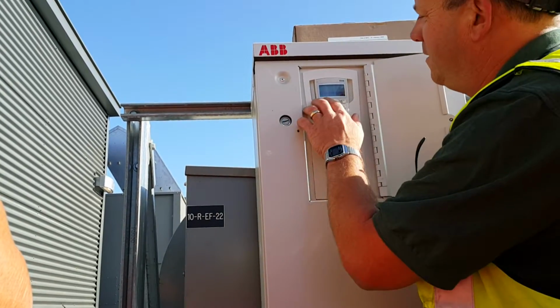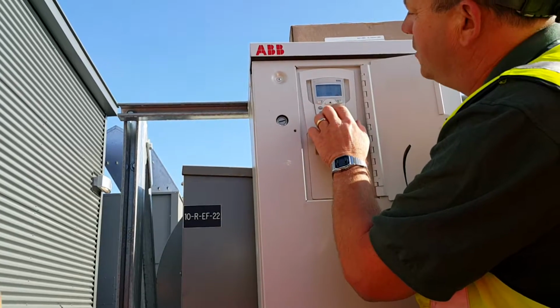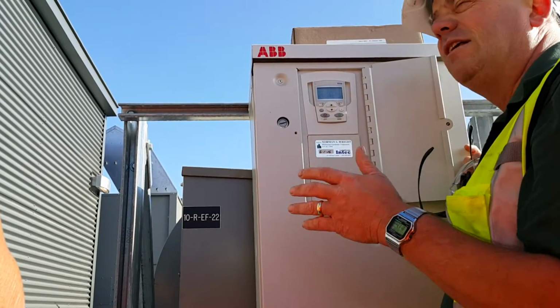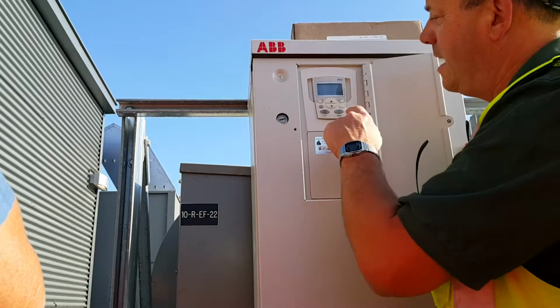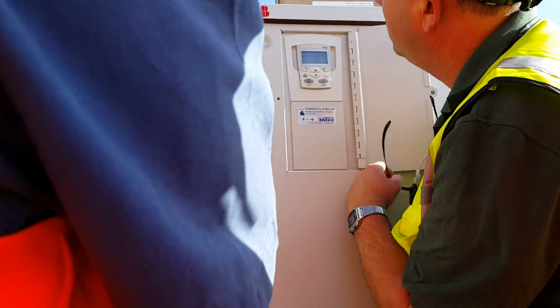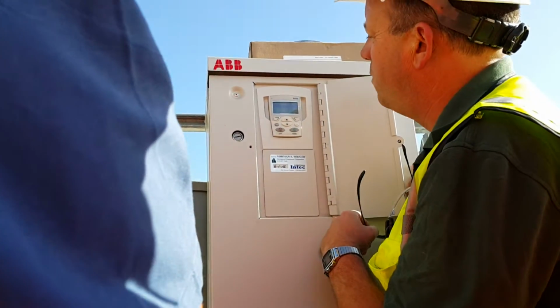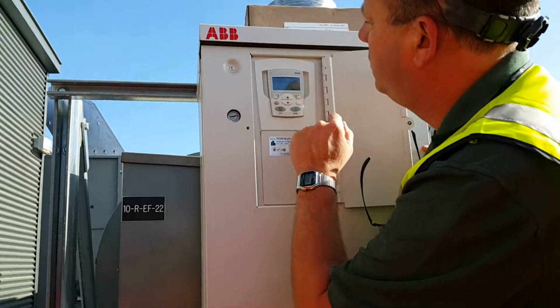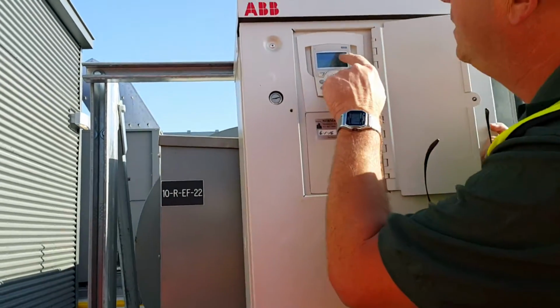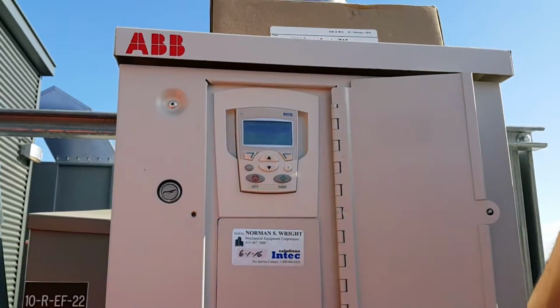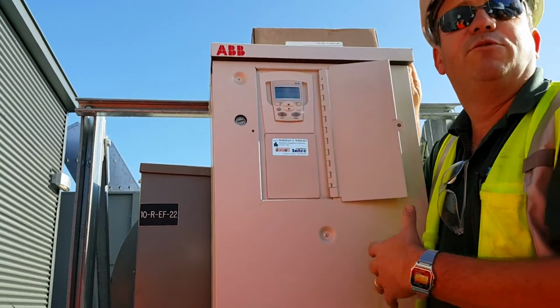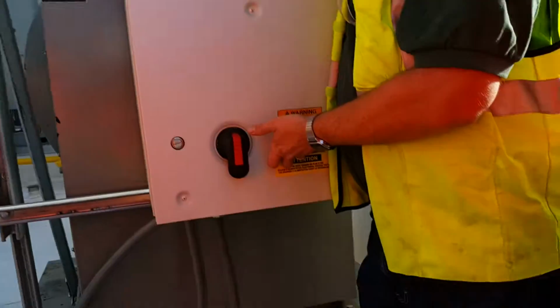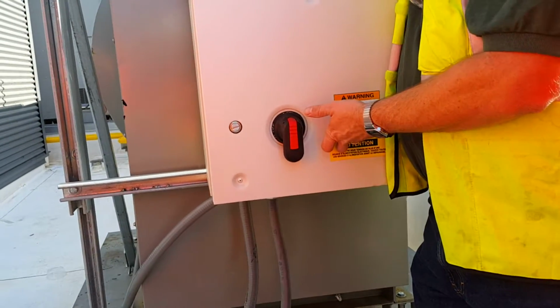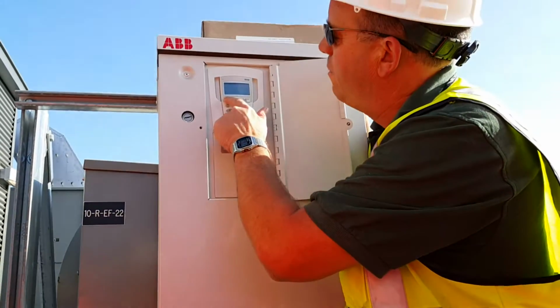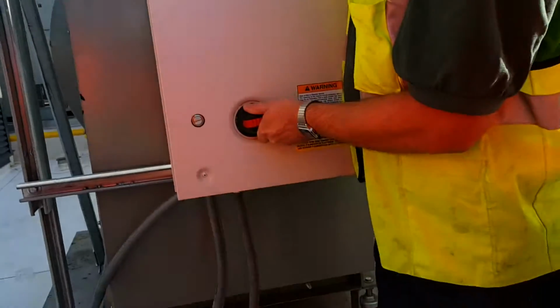Minimum frequency, 15 hertz. Another nice one is fault logger. It'll tell us our last faults with the day and time. So the last fault was a DC undervoltage on June 3rd, 2016 at 9:05. Undervoltage is not unlikely to see in the menu. That's any time it's running and power goes off. If we were to kick this out right now, it would go into an undervoltage fault. So anyway, why not see? Let's go ahead and do that.